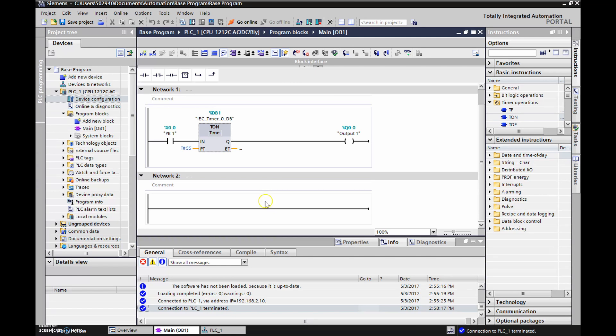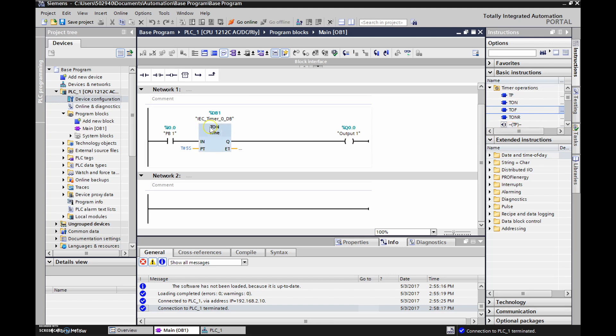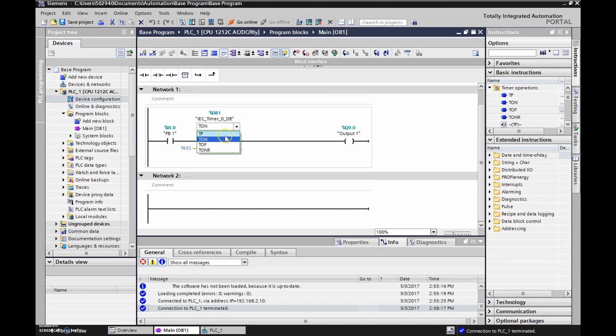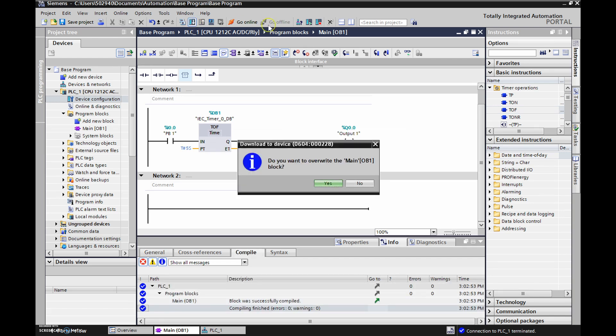Now we're offline and we're going to change this out to an off-delay timer. Instead of dragging from the instruction panel, let's hover over the TON symbol and double left click — that brings up a drop-down menu where we just change it to an off-delay timer. That's it — we have our input, our output, and our preset of five seconds. Let's download these changes to the PLC.